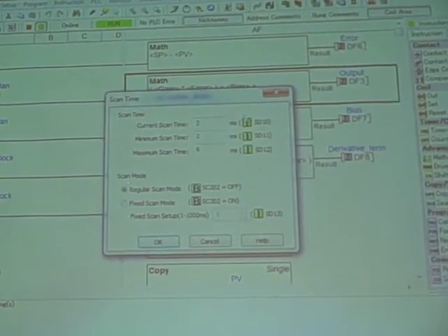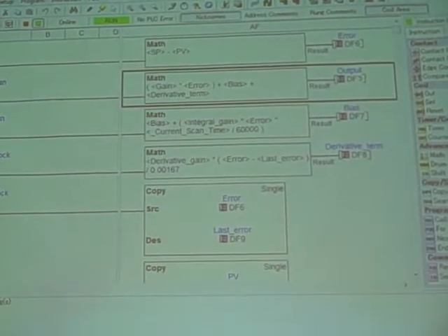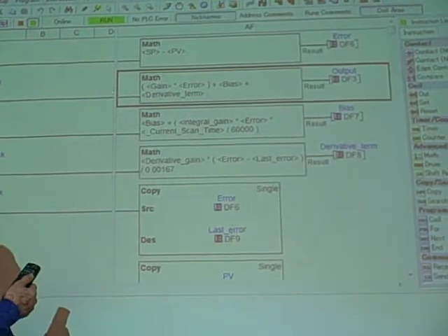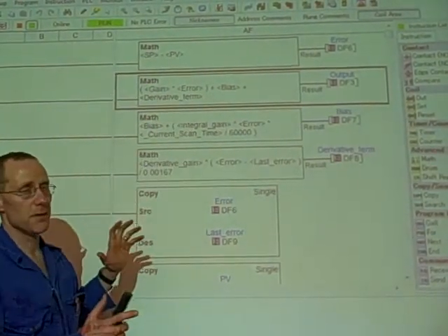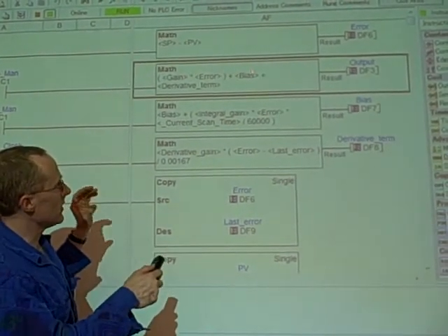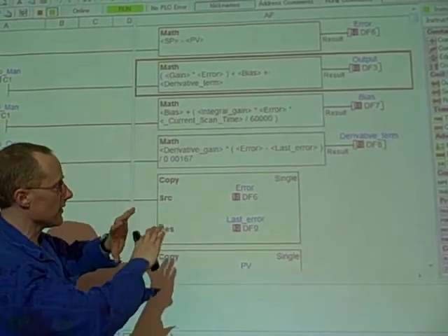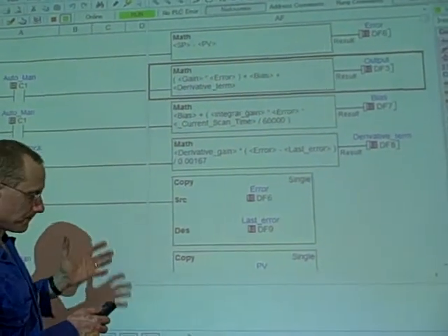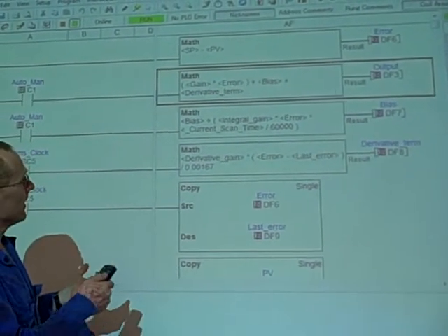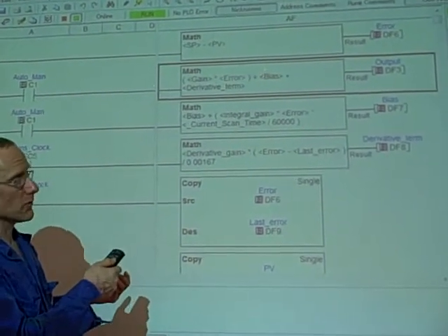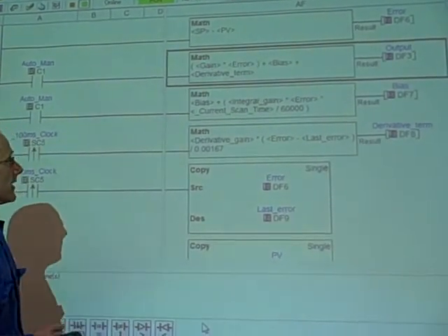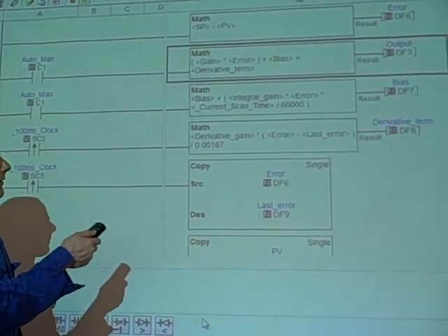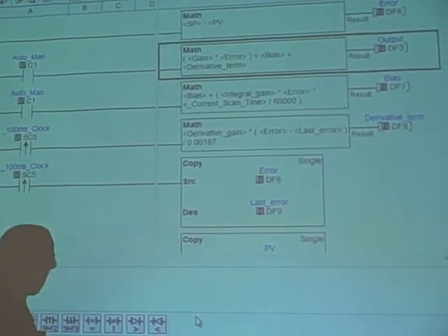So we've got a fully fledged PID control system. And by fully fledged again, I mean full P, I, and D control parameters. One more thing. This equation here is what they call a parallel equation. The P, the I, and the D terms are independent of each other. I can set the gain parallel, or sorry, the proportional down to zero. I can set integral down to zero. I can set derivative down to zero independently. It doesn't affect the other terms. Many other controllers use what's called the ideal algorithm. Some use what's called the series algorithm. And in that case, the gain that we use for proportional multiplies by all three terms. That's another variant we could have programmed in here. We could easily go back in the math statement and make it an ideal equation where the gain multiplies by all three terms. But in this case, we just went with what's simple.